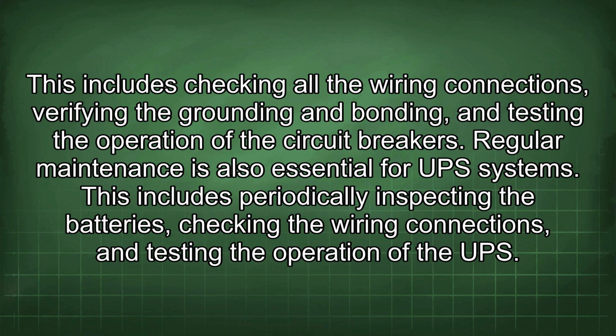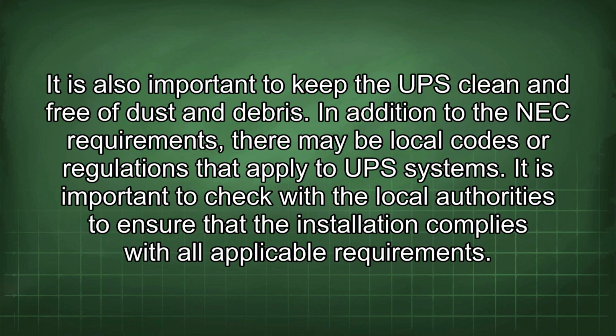breakers. Regular maintenance is also essential for UPS systems. This includes periodically inspecting the batteries, checking the wiring connections, and testing the operation of the UPS. It is also important to keep the UPS clean and free of dust and debris. In addition to the NEC requirements, there may be local codes or regulations that apply to UPS systems. It is important to check with the local authorities to ensure that the installation complies with all applicable requirements.